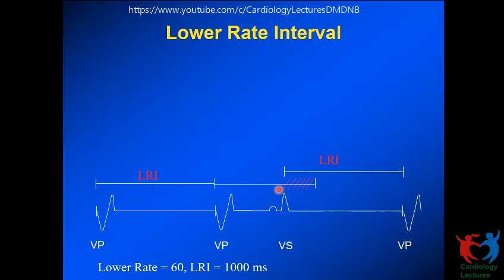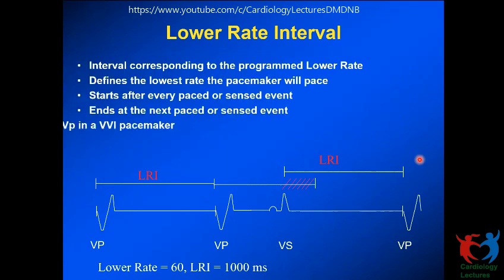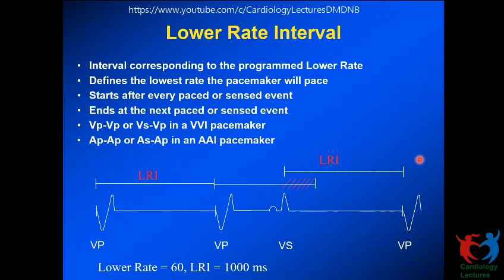So this is happening inside the heart. This is not in our control. So it's V pace to V pace or V sense to V pace. If you have implanted a single chamber atrial system, it will be A pace to A pace, and then A sense to A pace in an atrial alone pacemaker or an AAI pacemaker.